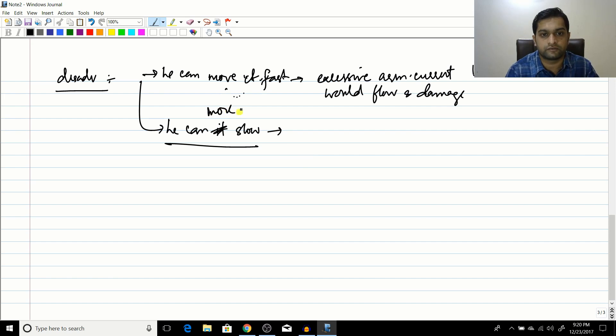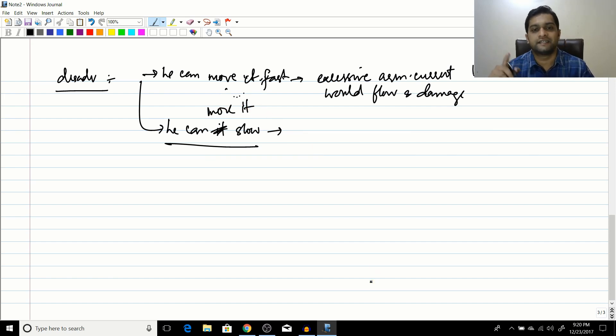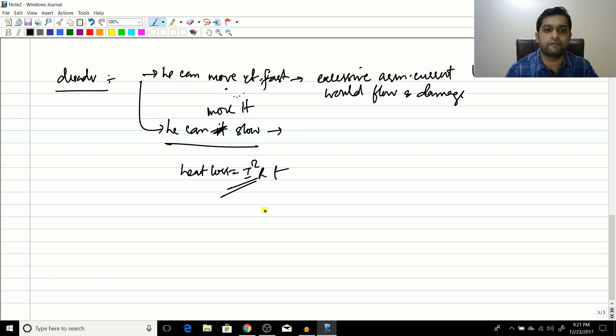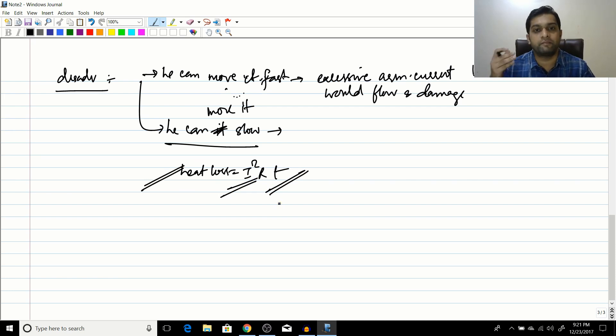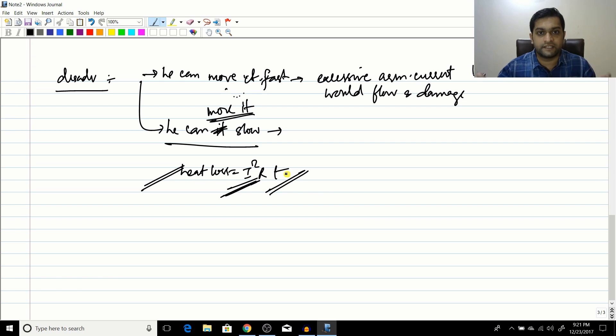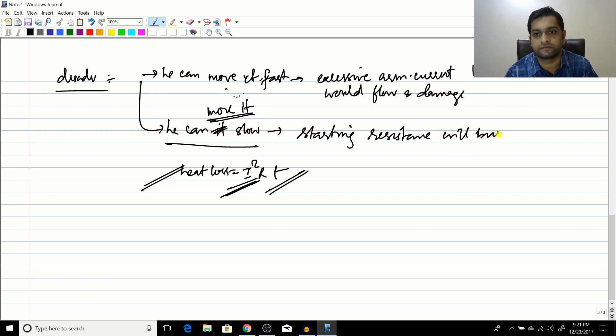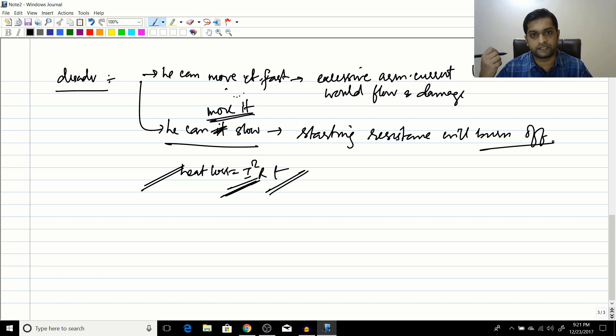If the operator moves the lever too slowly, the starting resistances carry the high armature current for a longer period. Since heat loss equals I²Rt, prolonged high current causes excessive heat and the starting resistances burn up because they are not rated to handle that much heat.